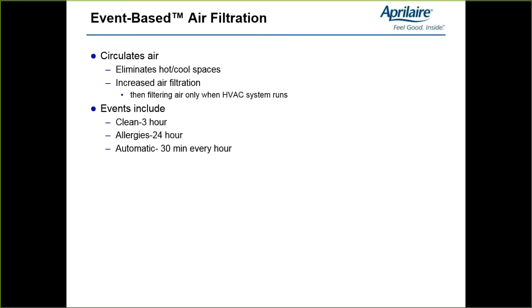So let's get into the actual makes and models of the thermostat. The 8810 is going to be our base thermostat. It's obviously Wi-Fi communications to the cloud or the automation system. Again, it's the universal thermostat. It has that event-based air filtration. This thermostat only supports an outdoor temperature sensor, so you can't have any flush mount temperature sensors. You can't put this in a mechanical room unless, of course, you want to control the temperature in the mechanical room. There's no humidity control.